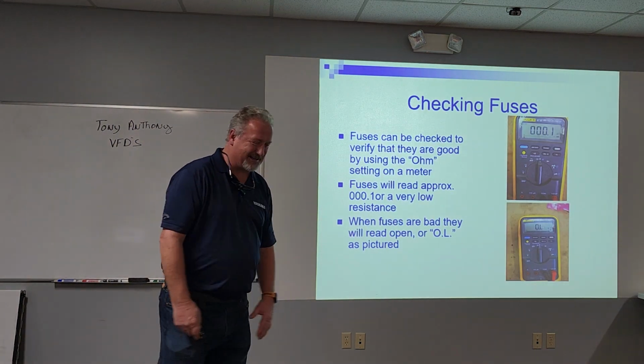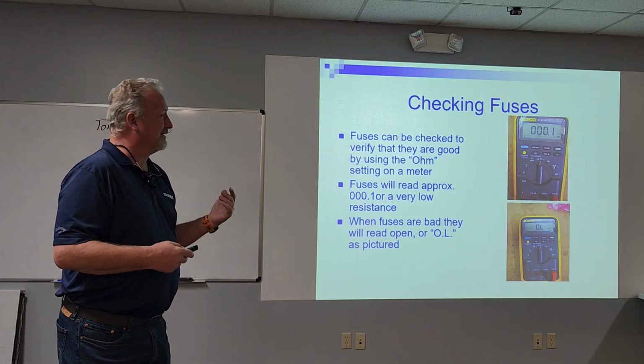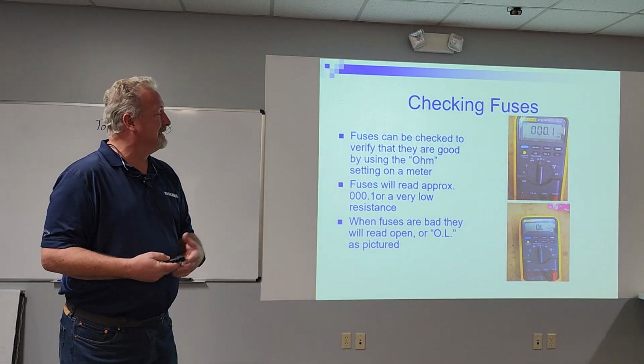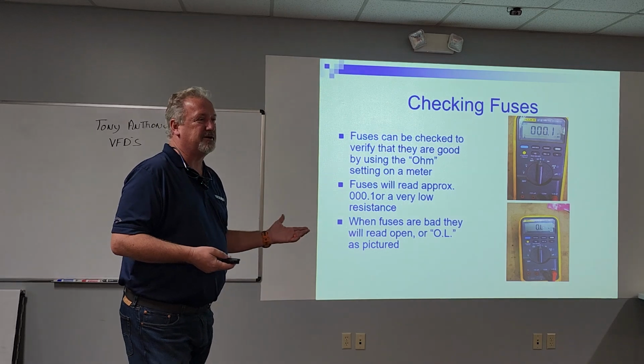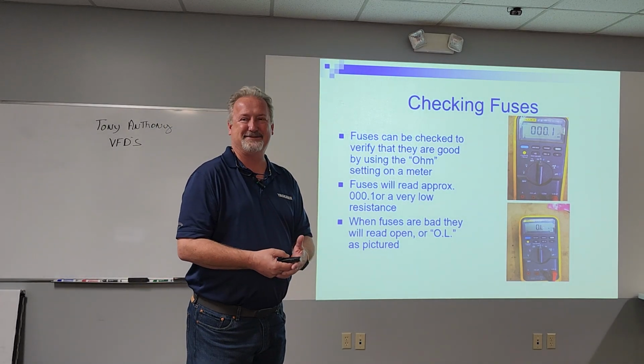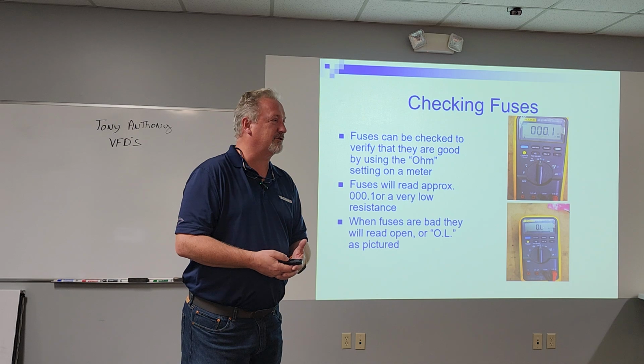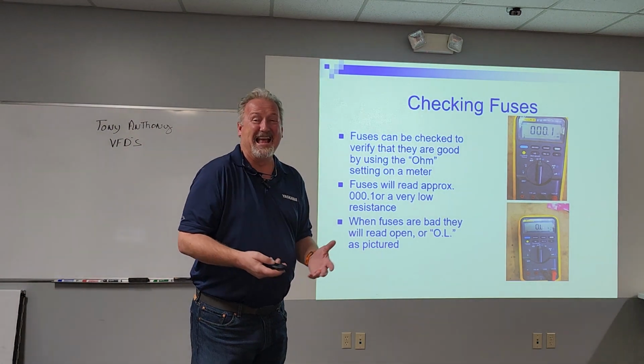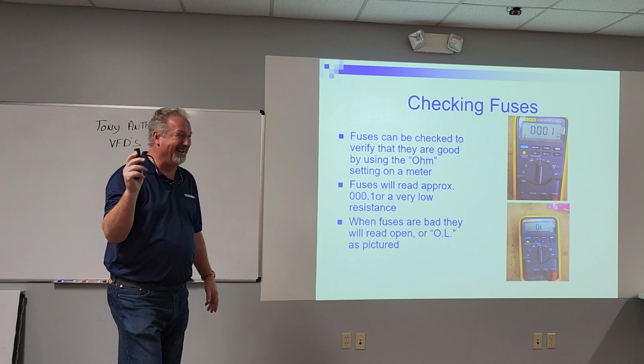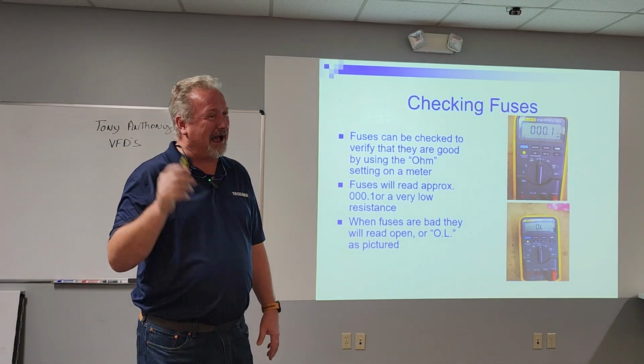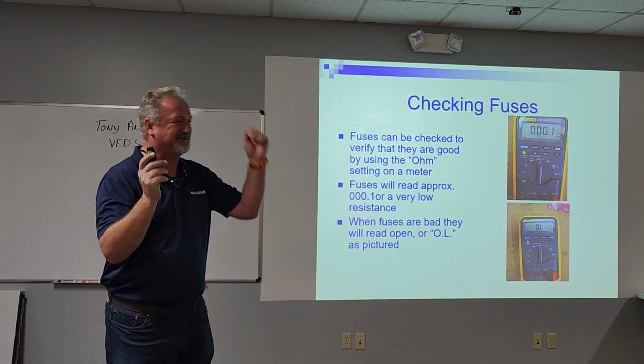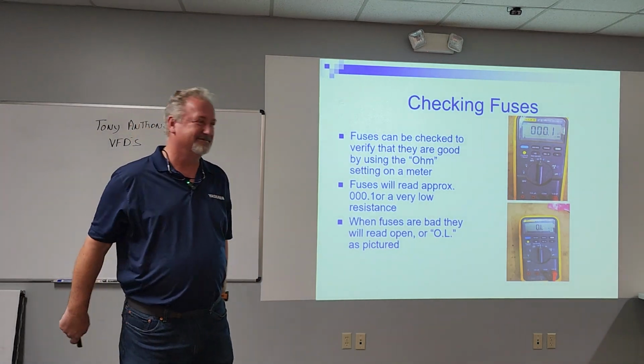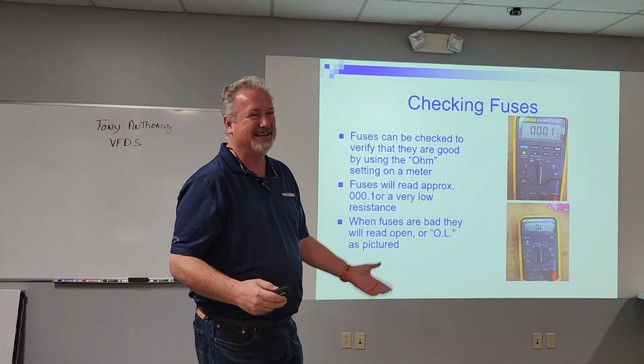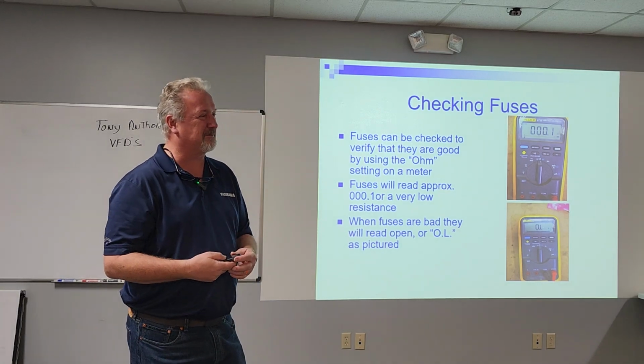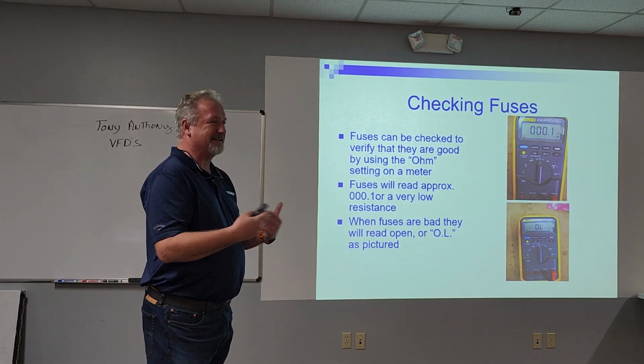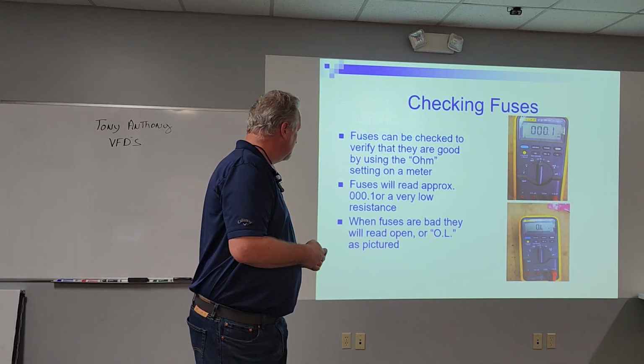The biggest thing about fuses, and I always get a kick out of this being in here, because you're mostly all technicians, but it's still a good reminder. To check a fuse, what's the number one thing you have to do? Take it out of the circuit. Yeah. We've all done it. I hate to admit it, I've actually checked fuses and read 6 ohms, it's good. No, I was reading a parallel circuit. So just a simple, easy reminder that sometimes you get in a rush and may forget. If you think you have bad fuses, take them out of the circuit and then check them to see if they're blown.